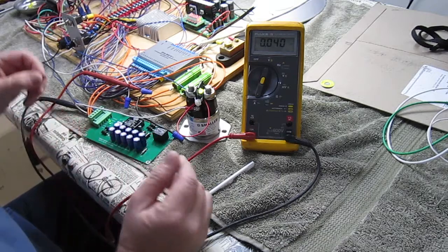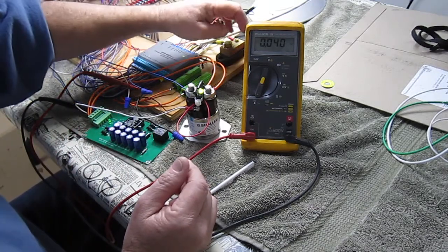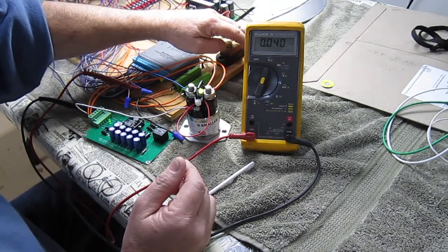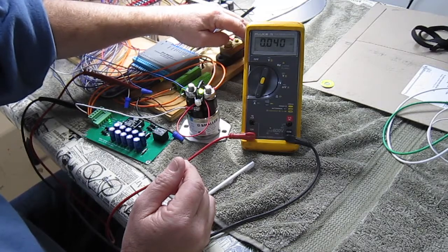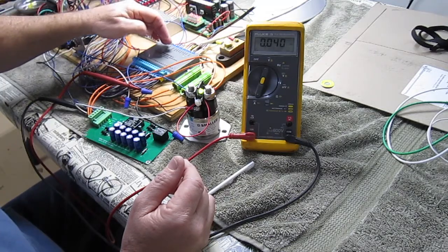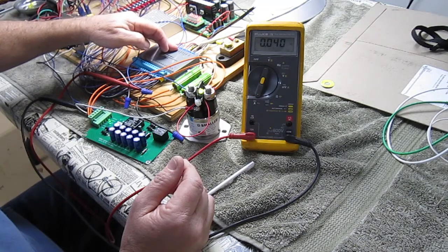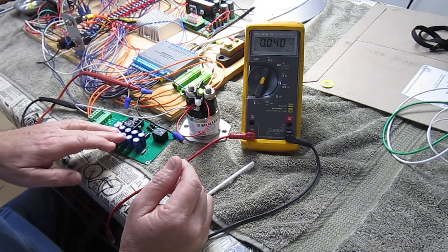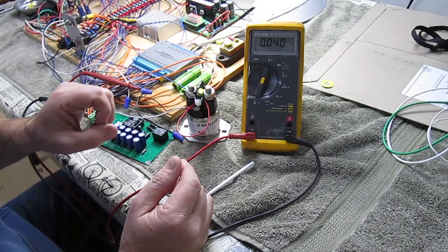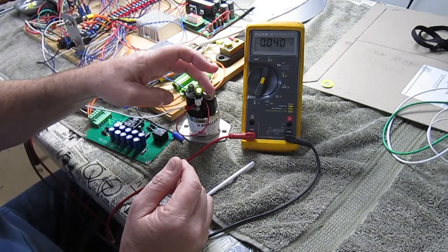In this case, I'm going to use the BMS and a cup of cold ice water to simulate an under temperature condition. The BMS relay will open and the capacitors will discharge into the open coil, and the pilot light will go out.